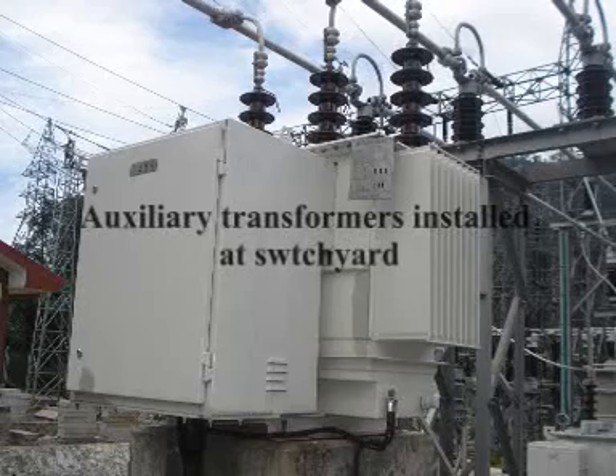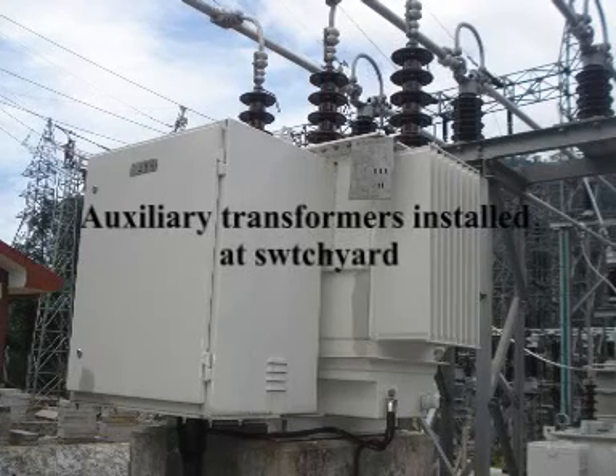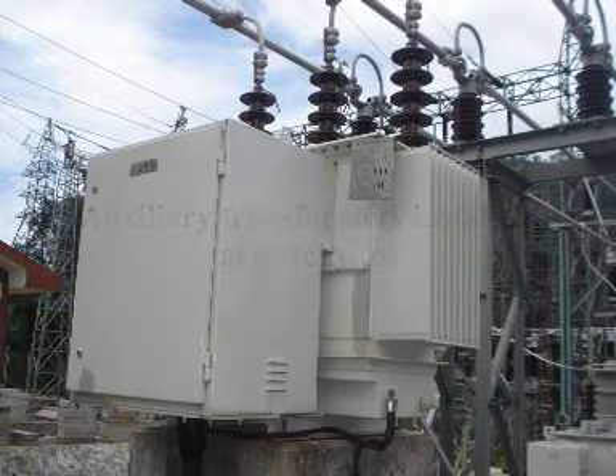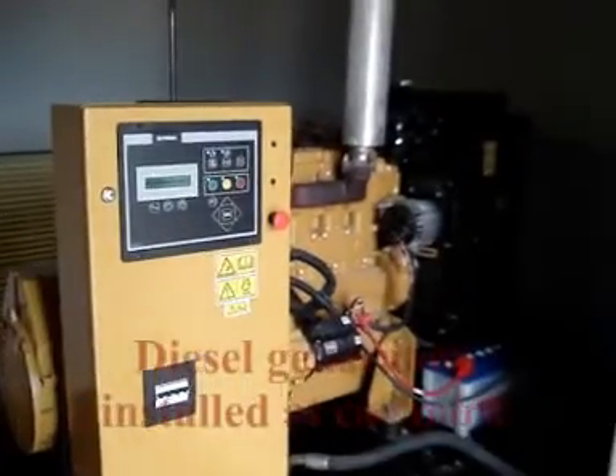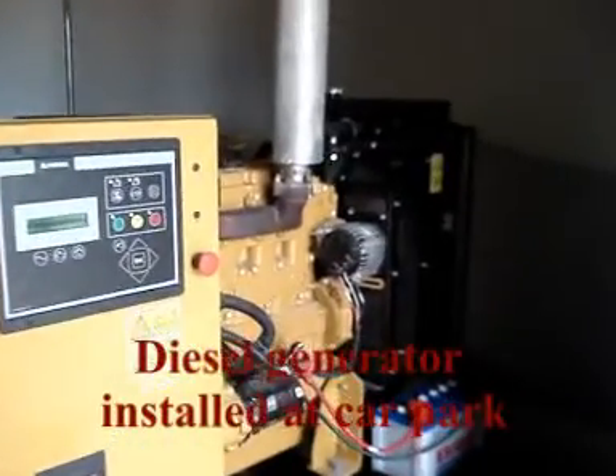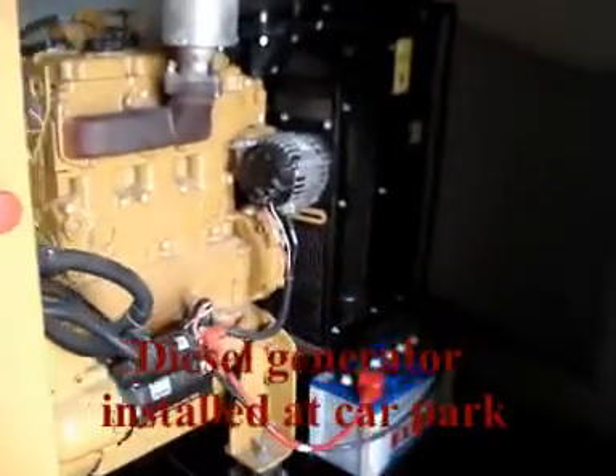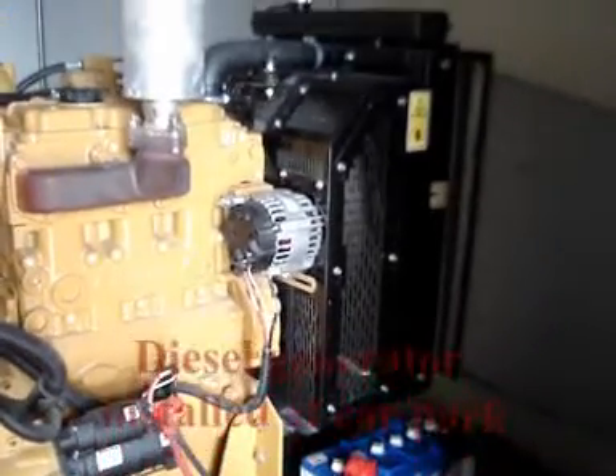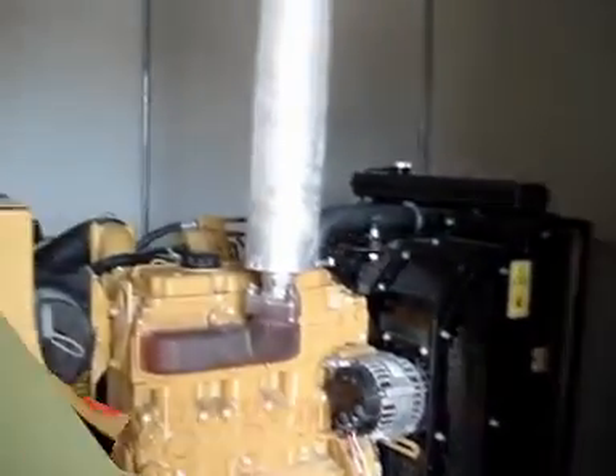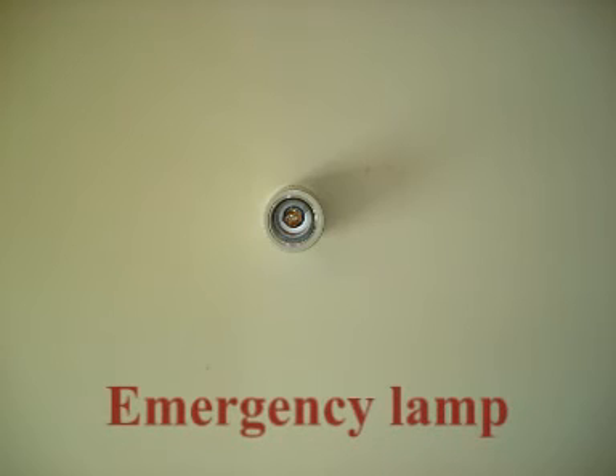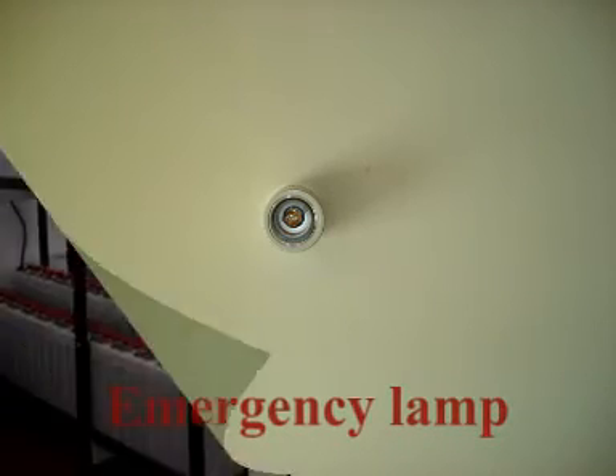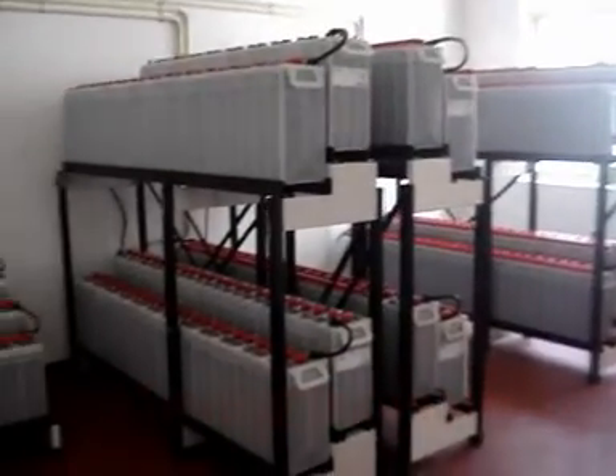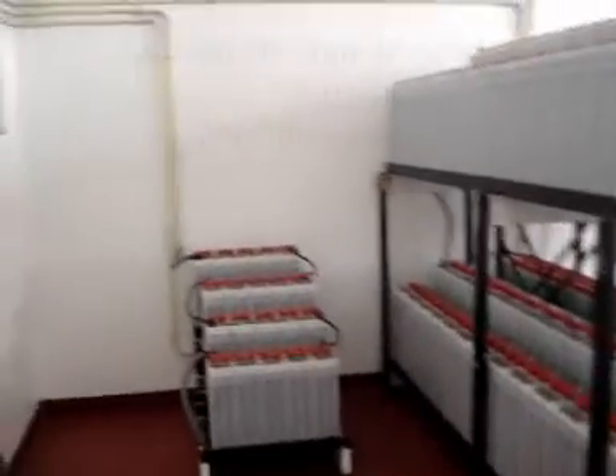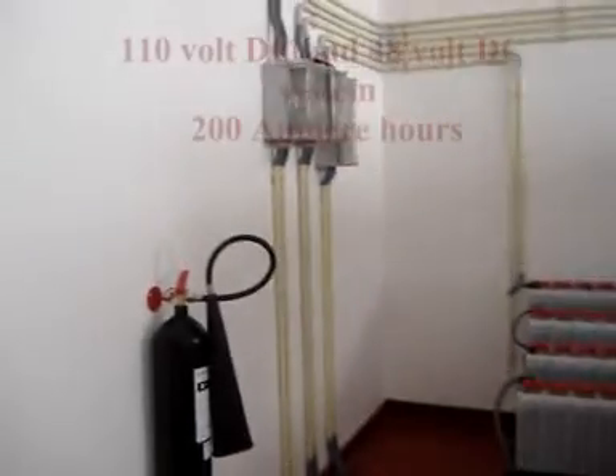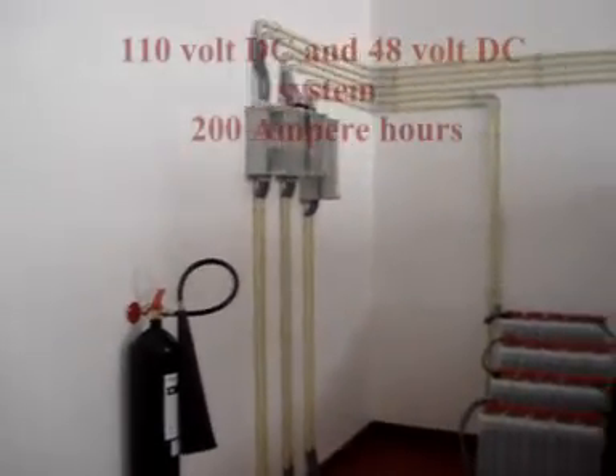Auxiliary supply to the substation is taken from one of the two auxiliary transformers installed at the switchyard at a time, and standby supply is taken from the standby diesel generator installed at the car park. However, an automatic emergency DC lighting system is also provided with limited lighting points inside the building to operate when none of the auxiliary supply systems are operative, including the standby diesel generator.